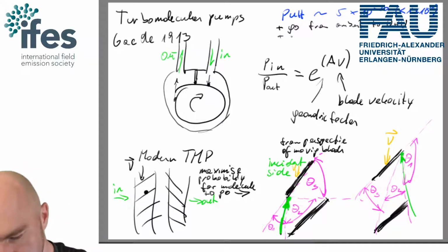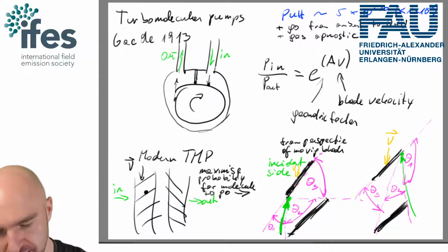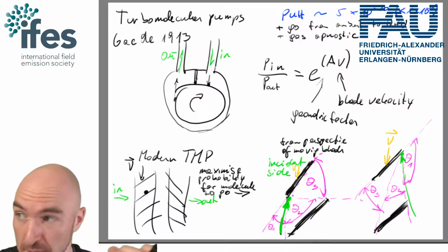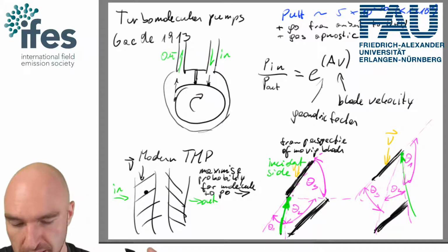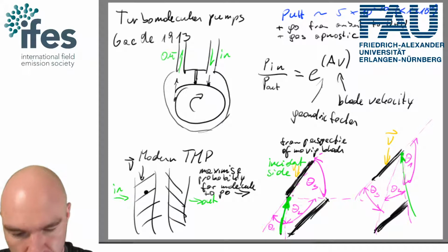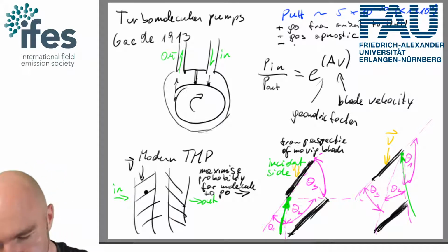They are gas agnostic largely, so obviously this is a momentum calculation, so the higher the momentum of the particle, the better it gets pumped, so heavier gases work better than lighter gases. They're just pretty simple in operation. The downside is that they are sensitive to pressure increases.